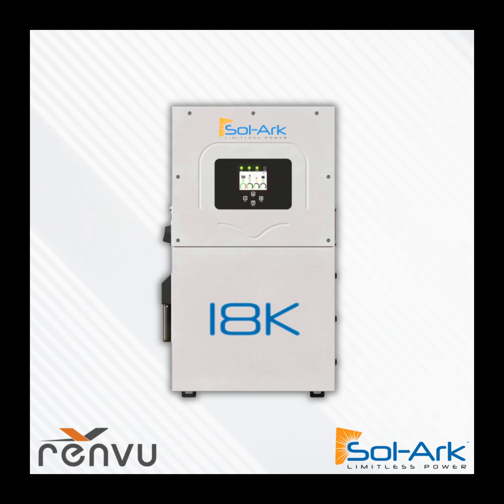Because when you design up to the peak load, the battery is sized well for peak shaving, and the battery and solar array are also sized well for load shifting. When you go above the facility base load with your solar array, all of that extra power has to be stored in a battery, and you can only go so far before the project turns into an off-grid project rather than a grid-tied project.